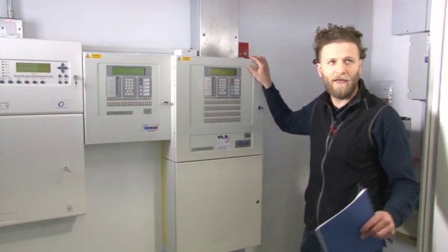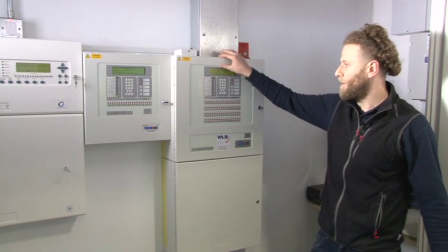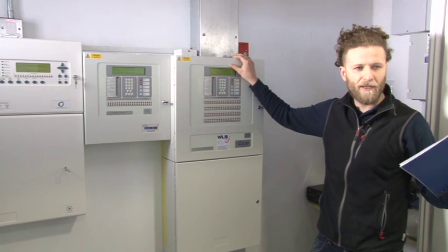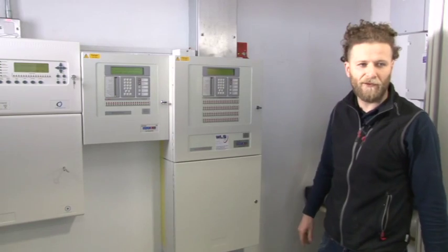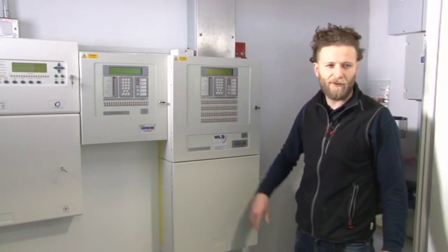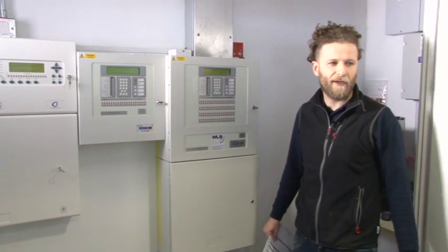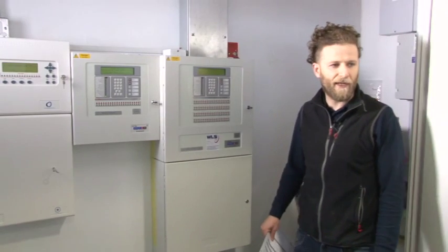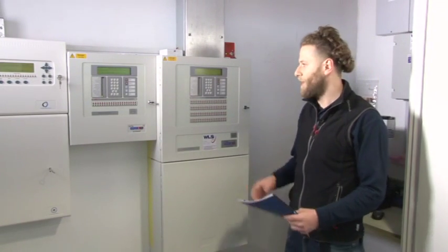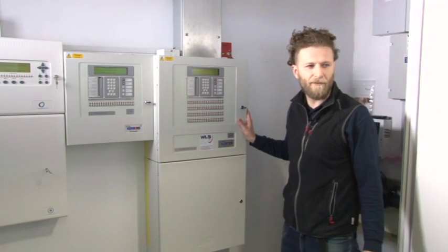Also, when there's a fire, one of the detectors will go off. For example, this one. You will see on the panel which zone it is and where the actual detector is. That's the main thing. Once you see which one it is, you have a 5-minute investigation period in most areas. Then you can go to the place and see what's going on. If there's any risk, you can alert the people to what happened and evacuate the building.